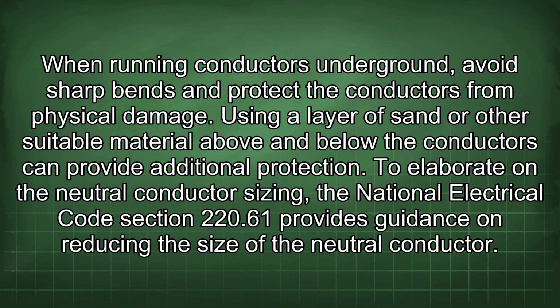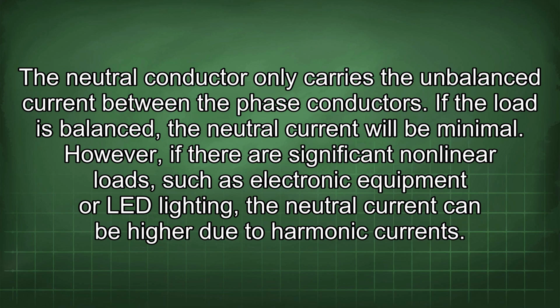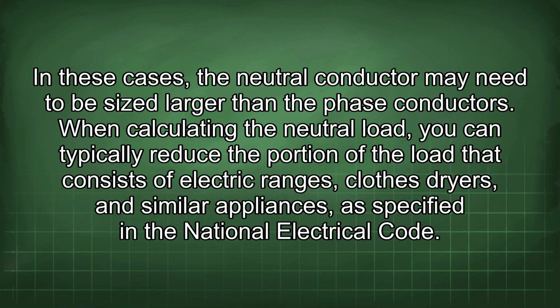To elaborate on the neutral conductor sizing, the National Electrical Code Section 220.61 provides guidance on reducing the size of the neutral conductor. The neutral conductor only carries the unbalanced current between the phase conductors. If the load is balanced, the neutral current will be minimal. However, if there are significant nonlinear loads such as electronic equipment or LED lighting, the neutral current can be higher due to harmonic currents. In these cases, the neutral conductor may need to be sized larger than the phase conductors.